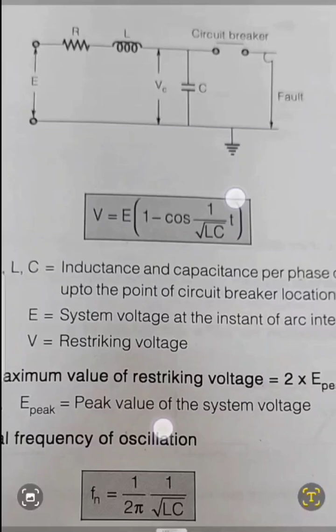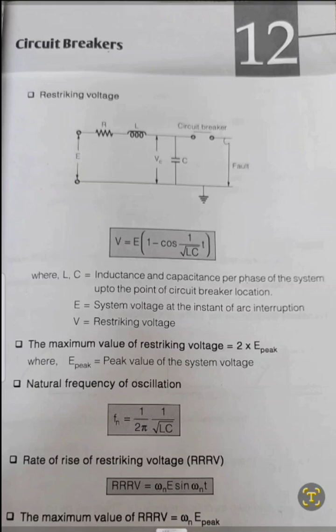The maximum value of restriking voltage equals 2 times E peak, where E peak is the peak value of the system voltage. The natural frequency of oscillation Fn equals 1 by 2 pi root over LC. The rate of rise of restriking voltage (RRRV) equals omega n times E sin(omega n t), and its maximum value equals omega n times E peak.